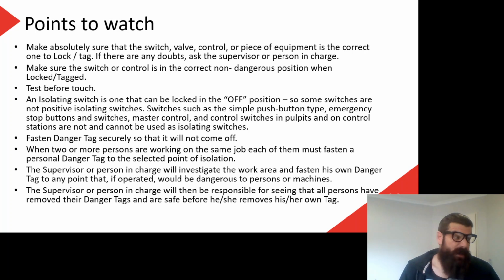We need to fasten our danger tag securely so it doesn't fall off. That should be obvious. We've got two people working on the same job. We must each have our own tag and lock. We've seen before that you can have multi-lock, so we put that lockout device on the isolator or circuit breaker, and then multiple people can have their own locks and tags, and we should do that. Every single person must have their own lock and tag, so we can't accidentally liven something while there's still someone working on it. We all have to take off our own individual locks before that can be relivened.